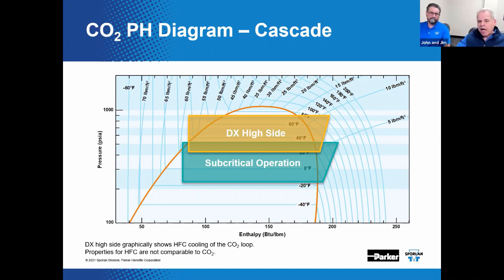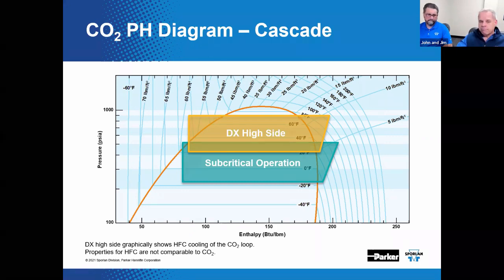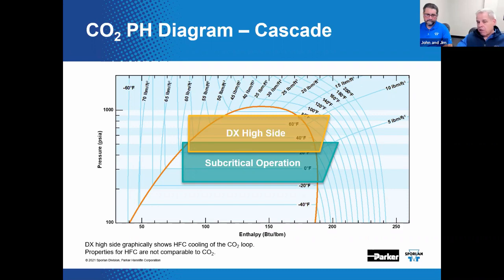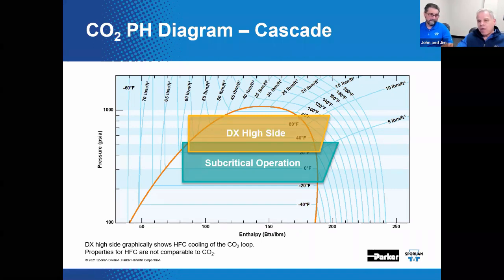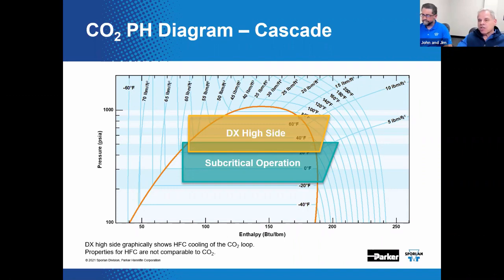The refrigerants are selected to optimize operating efficiency in the respective temperature range. Each part of the cycle produces an effect sequentially lower in temperature in order to span the needed temperature range and ultimately produce the desired operating conditions. Again, the DX high side would utilize an appropriately selected HFC, HFO, inorganic refrigerant like an NH3, or HC refrigerant, and it would have different properties as compared to CO2. From that standpoint, what we've depicted here is not totally technically accurate because we're showing two refrigeration cycles on one pH diagram. It's diagrammatically correct, but you cannot technically do that with two different refrigerants on it. So it's just for illustrative purposes only. Yep.